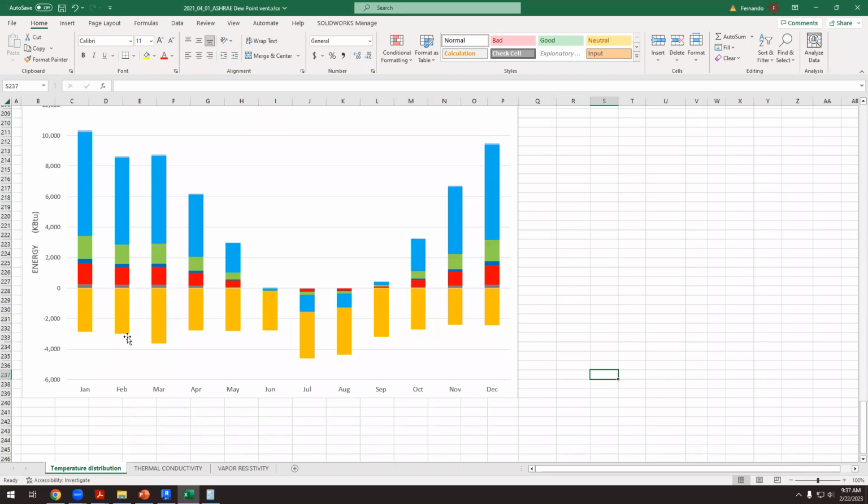So in this building, with that amount of glass, there are 2 months in which, if we didn't have any glass, we would have this heating load. But having this glass makes up for the heating load that we have in these 2 months. And even in January, we have this extra heating that is for free. So we have to subtract the actual value minus the heat gains that we have due to the sun.